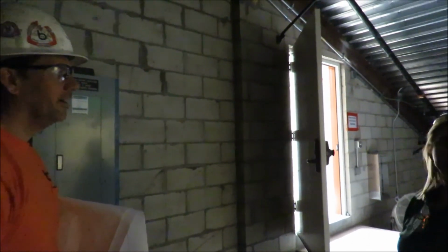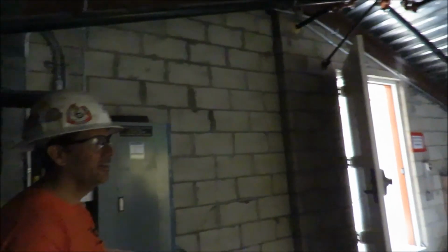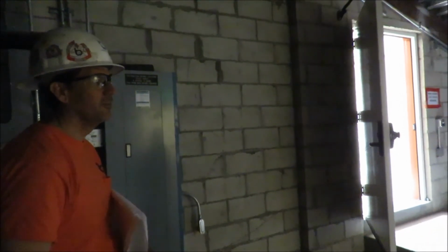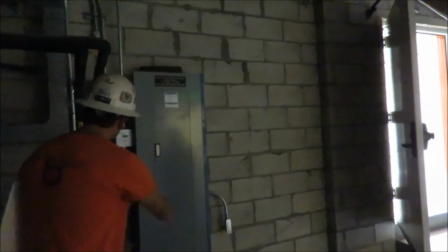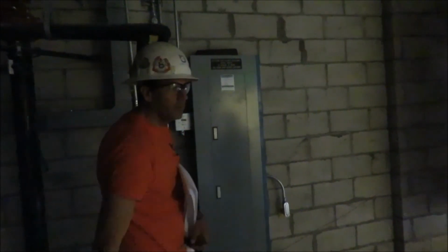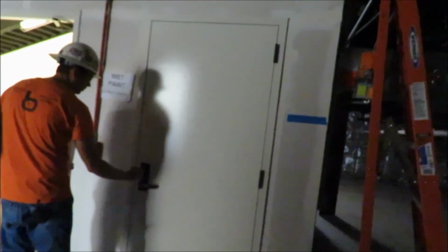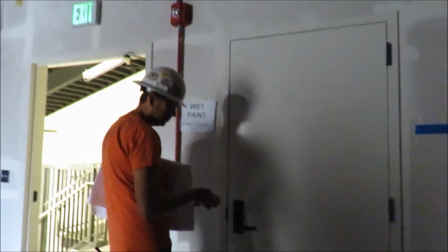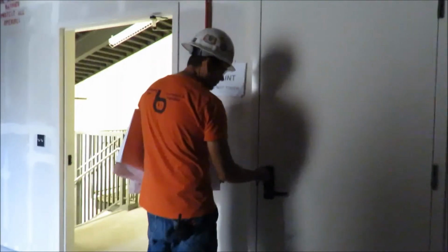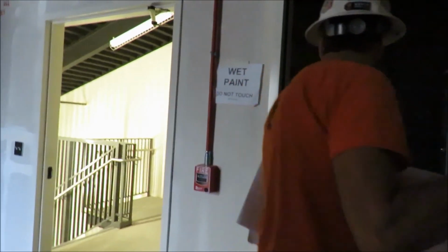That's cool. So that's important to know. It makes it easier, because usually when you're under pressure, people are like, "Hurry, reset the elevator," and you're like, "Just a minute." So here's your shunt trip wires, and the breaker's right in here. I think also in your elevator room, if your heat detector goes off, it does a shunt trip. It's always good to know where it is.